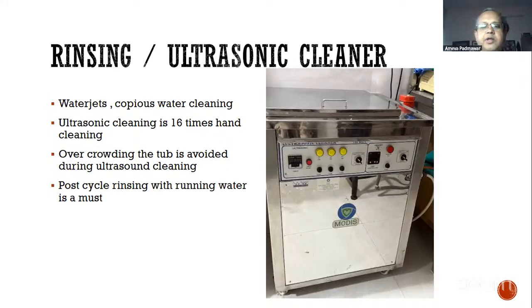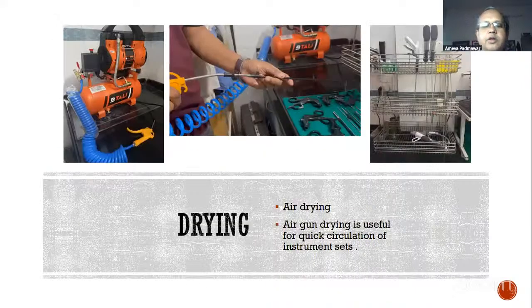And every center which caters to more than one laparoscopy or hysteroscopy procedure in a day should have this. Of course, after the cycle, you have to clean all these instruments with running water, because water is going to reach into every channel and groove and get rid of whatever has been dislodged. Then comes the drying part of the instrument. So this is the small air compressor in our clinic, and that's how we use the air jet to get rid of all the moisture from inside of these small tubular instruments.